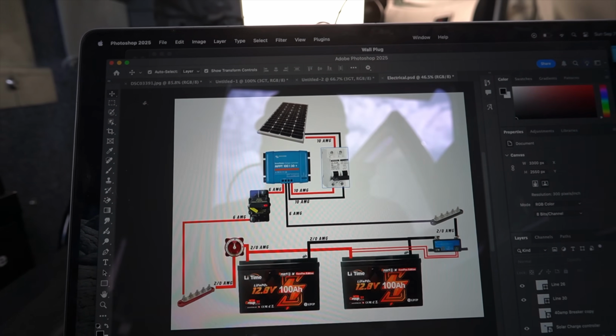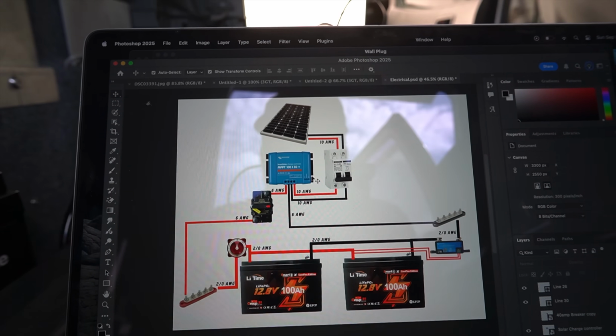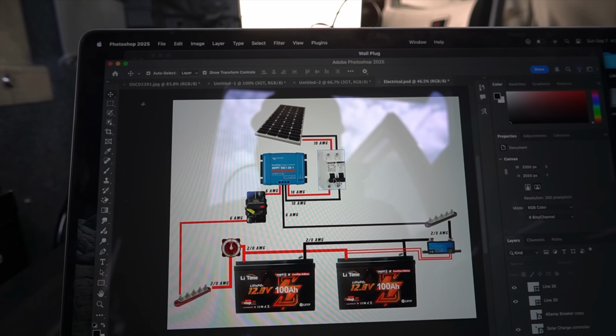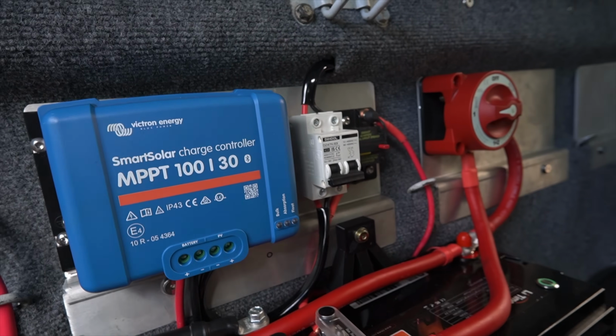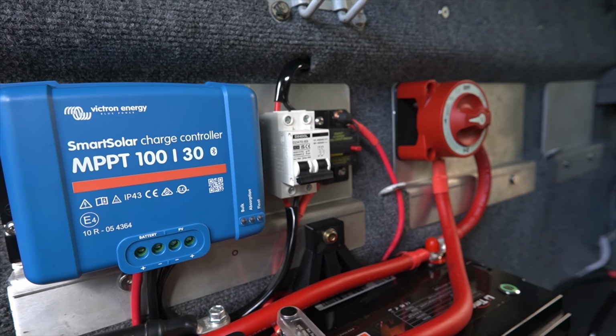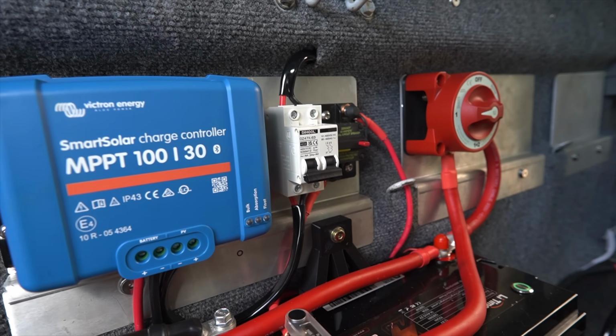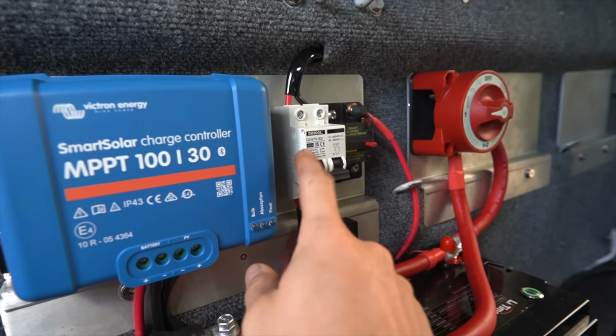Now going to our solar panel itself, we've done 10 gauge wiring with a dual pole breaker. The reason we do a dual pole breaker is for solar, you want to protect both sides of the circuit, the positive and the negative. If you truly want protection from any faults, you're going to want to do a dual pole.